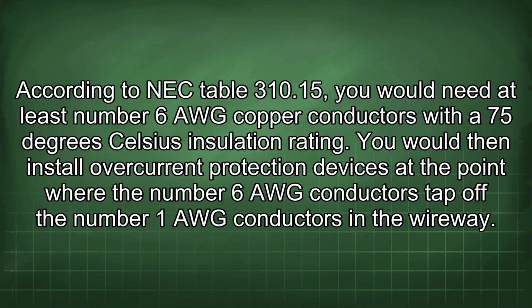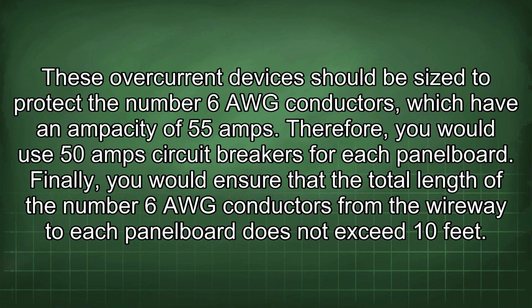insulation rating. You would then install overcurrent protection devices at the point where the number 6 AWG conductors tap off the number 1 AWG conductors in a wireway. These overcurrent devices should be sized to protect the number 6 AWG conductors, which have an ampacity of 55 amps. Therefore, you would use 50 amp circuit breakers for each panel board.